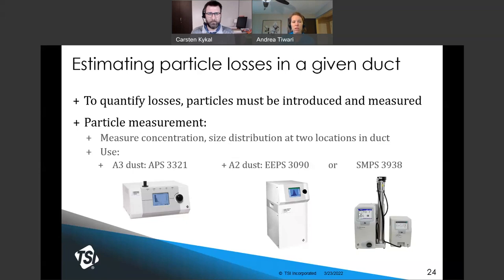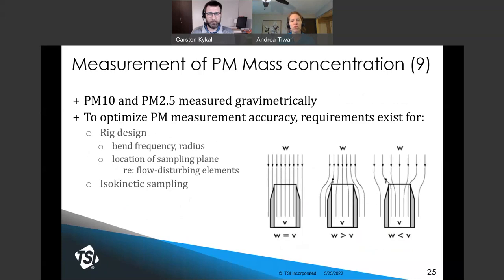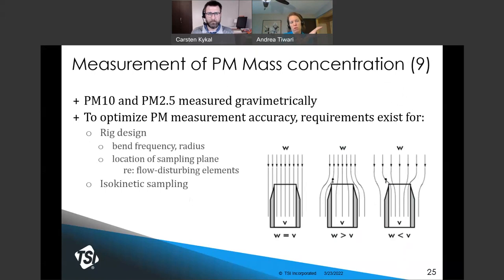Now that loss estimates have been made, the final piece is in place for making accurate measurements of particle mass and particle number emissions. The protocol addresses particle mass measurements first, in Section 9, using the metrics of PM10 and PM2.5 — particles smaller than 10 micrometers and 2.5 micrometers, respectively. Requirements pertain to bends in the airflow path, the radii of those bends, and the location of the sampling plane — a vertical plane across the duct through which the system's air and particles are flowing. Sampling at that plane must be conducted isokinetically.